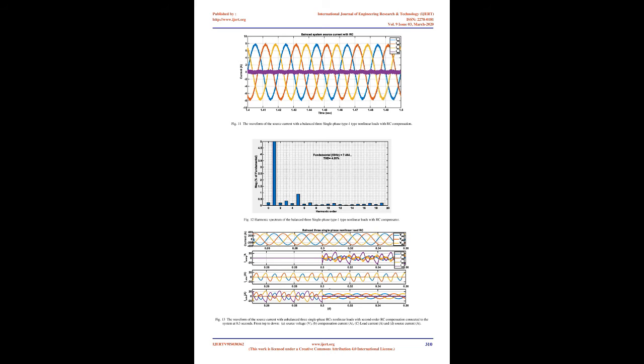Unfortunately, the zero sequence currents of the phase lines are not cancelled out at the junction of the neutral line; instead they sum up and create a burden for the system. Notice that the well-known theory that a balanced three-phase system has zero neutral current works only for linear loads. Therefore, balancing the three-phase loads will not guarantee zero neutral current. Fig 10, harmonic spectrum for the balanced three single-phase type 1 nonlinear loads.